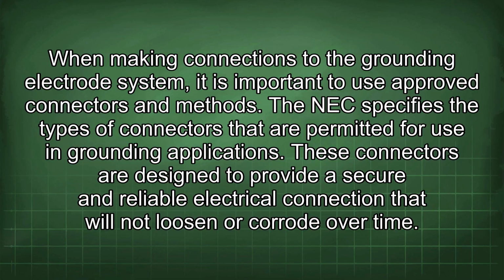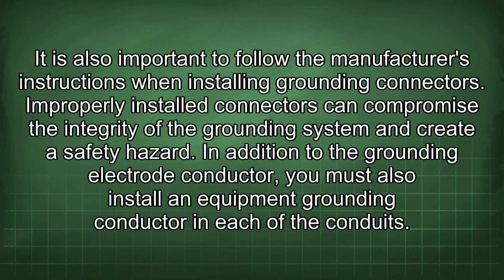When making connections to the grounding electrode system, it is important to use approved connectors and methods. The NEC specifies the types of connectors that are permitted for use in grounding applications. These connectors are designed to provide a secure and reliable electrical connection that will not loosen or corrode over time. It is also important to follow the manufacturer's instructions when installing grounding connectors. Improperly installed connectors can compromise the integrity of the grounding system and create a safety hazard.